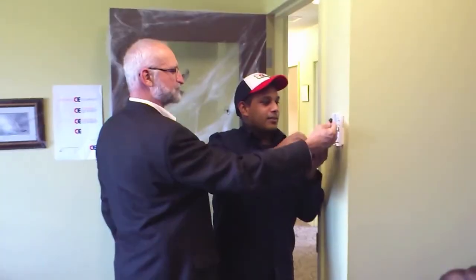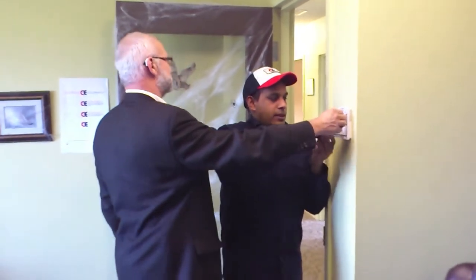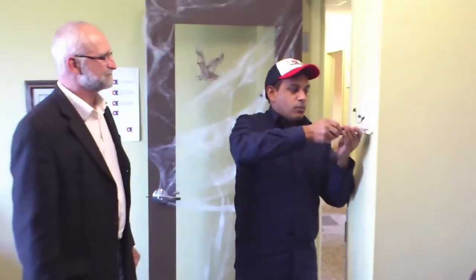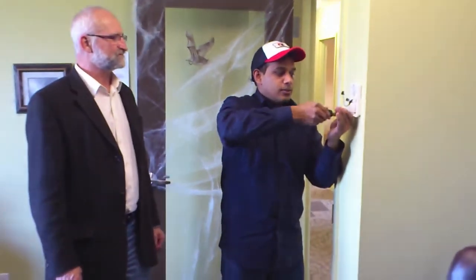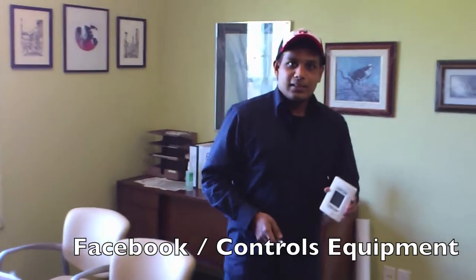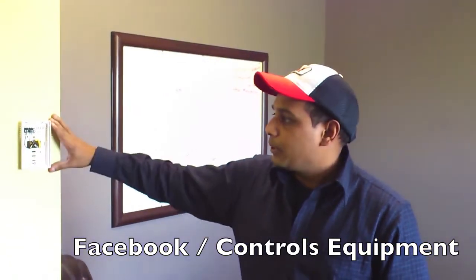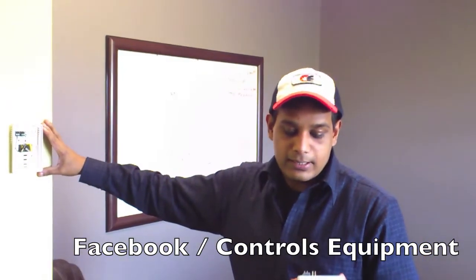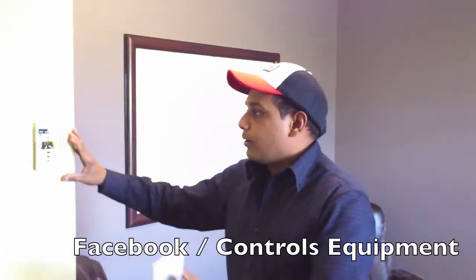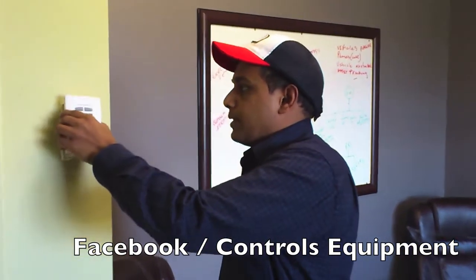Yes — including wire fittings. You don't have to take off the power, and you don't have to take off the network cable. Basically we're going to reuse the wire fittings from the old DNS onto the new DNS. DNS stands for Delta Network Sensor, and it runs BACnet protocol. After we finish taking off the old DNS and putting on the new back plate for the DNS-CHM24, I'll reuse the wires and two-wire connections — just snap this on and it should work.